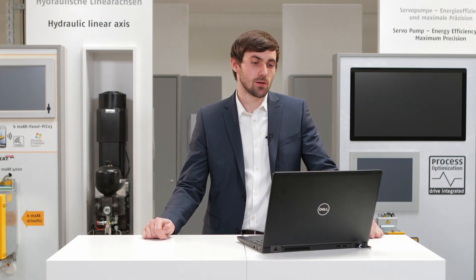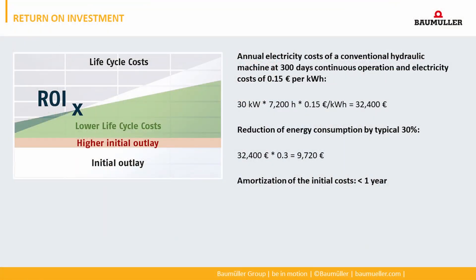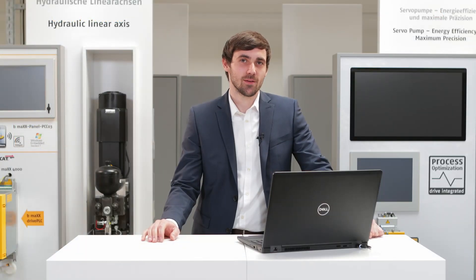This slide shows a typical return on investment calculation for a hydraulic machine. We assumed a medium power of 30 kilowatts at 300 days per year, with electricity costs of 15 cents per kilowatt hour. This results in energy costs of over 30,000 euros per year. If a typical saving of 30% is expected, this results in a reduction in energy costs of around 10,000 euros. The amortization time for the higher initial costs is typically less than one year. In general, savings up to 50% are possible.